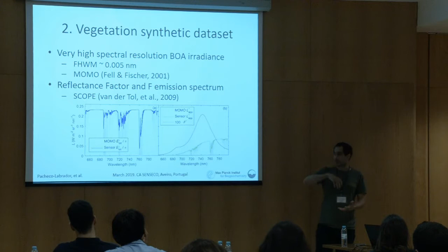And because of the data we were receiving, we didn't have data for irradiance, so we did this easy conversion and assumed that we could go from radiance to irradiance. This is how we simulated the uncertainties of our lamp, and we use this lamp to characterize the instrument data. These are some of the responses that we simulated. Some of them came from actual experiments, so we knew the response. We didn't use the response with uncertainty, just a perfect response, and from there we put in uncertainties from this lamp and also from the noise of the sensor and so on, and then we generate a calibration file with some uncertainty. We also use the data from the spectral calibration, from the work that Laura showed before.